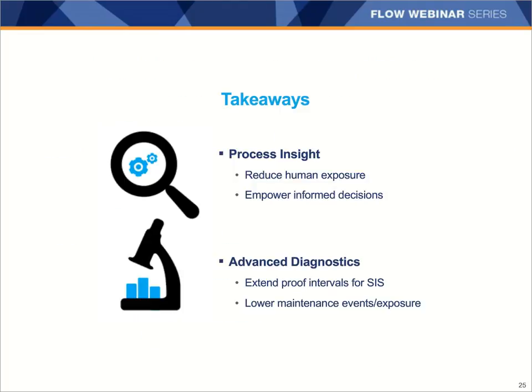So at this time, I'd kind of like to begin wrapping up. I'd like to remind you that advanced measurement technologies offer really significant opportunities for improving safety, whether it's through improved knowledge of the process itself that allows for advanced notification of any kind of potential dangers and allows you to make better choices, or whether you're looking at some of the advanced diagnostics that are offered today that can actually help extend proof testing intervals, reduce your probability of failure on demand, or reduce traditional maintenance and shutdown events.